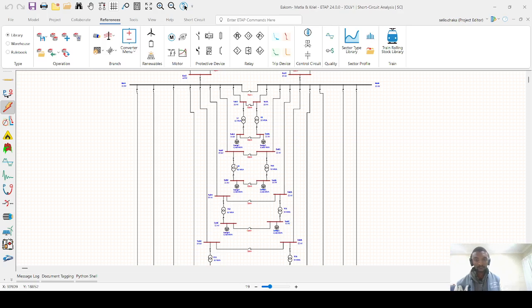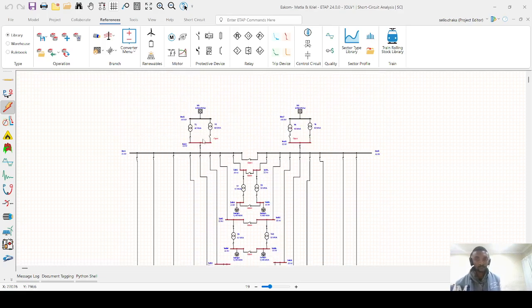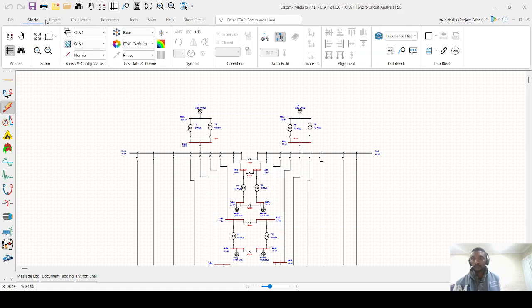Since the 11 kV substation is fed via a 22 kV transformer from the upstream substation, in this case this is the 11 kV substation fed from the upstream 22 kV common bus, which is stepped down by this 22 to 11 kV transformer. For the generator transformers, the primary side fault level equals or exceeds the 22 kV feeder buses due to the proximity to the Kriel and Matla power stations. So I am going to run that.